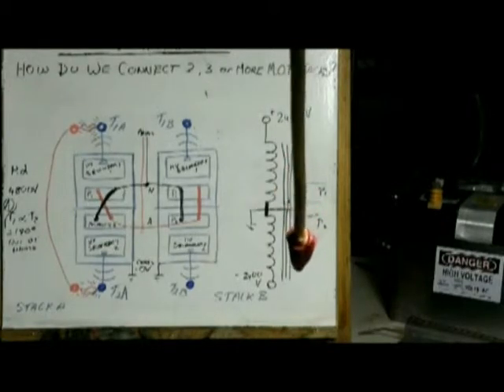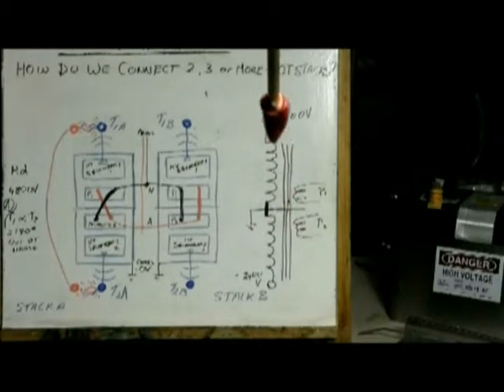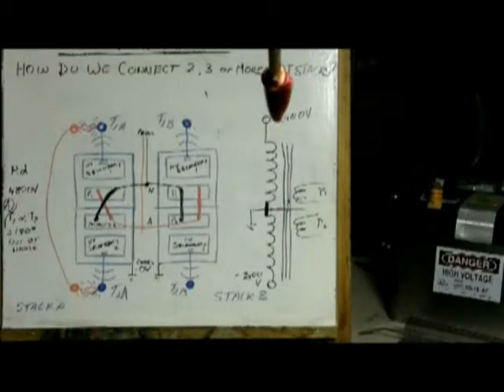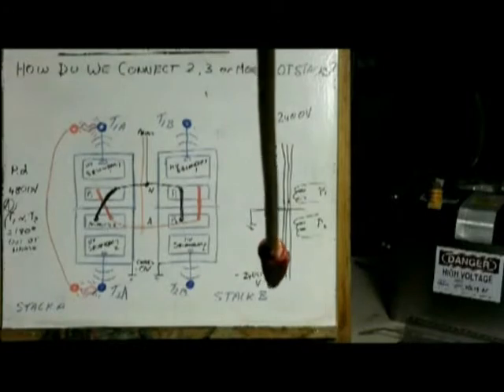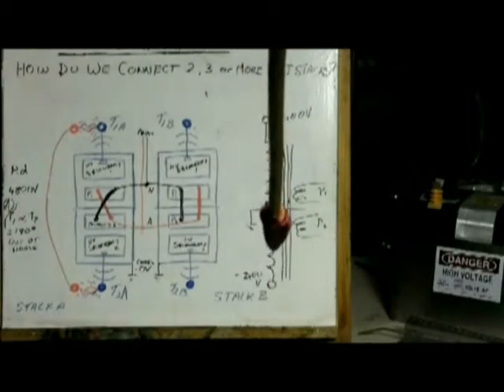Okay, the circuit diagram which just appeared here to the right describes the situation that we have at the moment. Both stacks have this situation. You can see the cores. You can see the primaries, primary 1 and primary 2, which correspond with that. The secondary windings are the big windings there. The terminals, T1 and T2. The cores are grounded at the moment. You have 2,400 volts on one side, and when it's plus on one side, it's 2,400 volts minus on the other side. And of course, because alternating current and they're 180 degrees out of phase, it reverses, maintaining a potential difference of total of 4,800 volts. But that's not what we want.